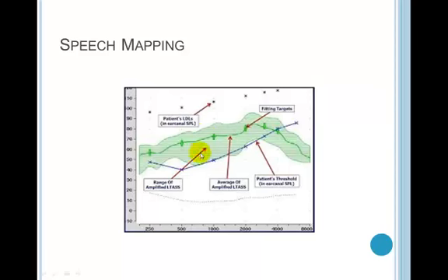This shaded area is the long-term average speech spectrum, where the targets are going to fit right in the center. So as the running speech is going, the man's going on and on at a normal conversation level about how carrots are grown, we're actually seeing how much gain is going. So how that sound is being picked up from the hearing aid microphone, sent through the hearing aid and processed into the patient's ear, and how close are we getting to target.